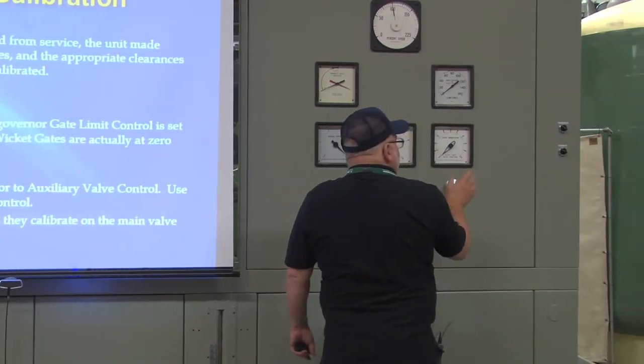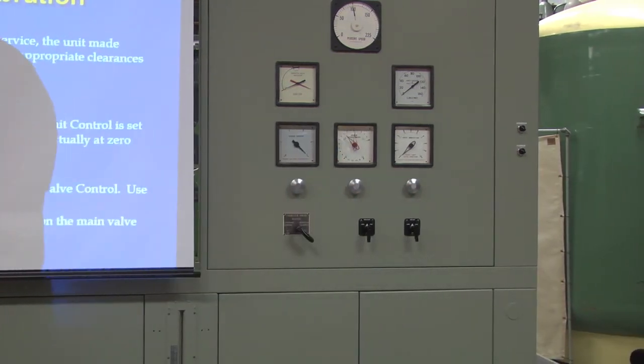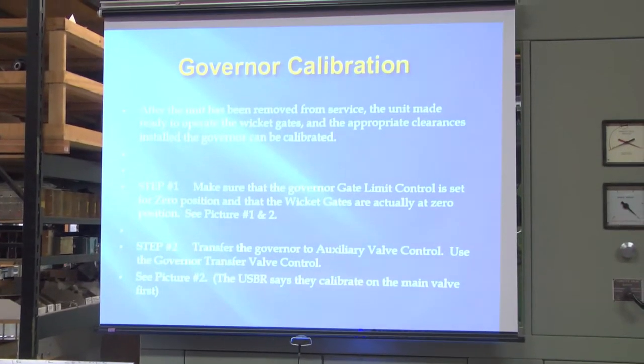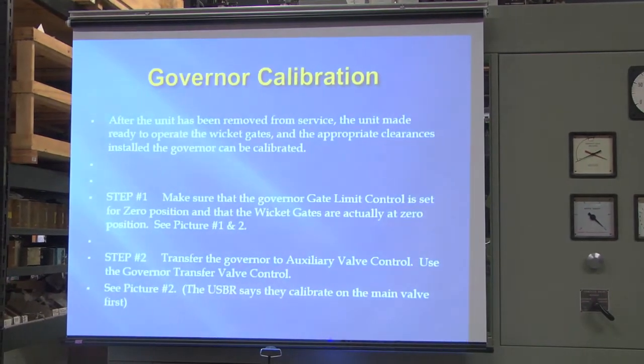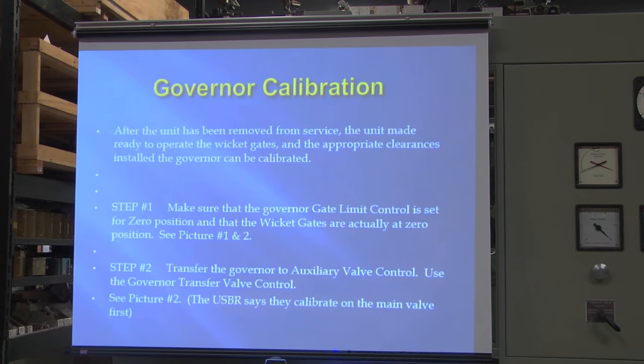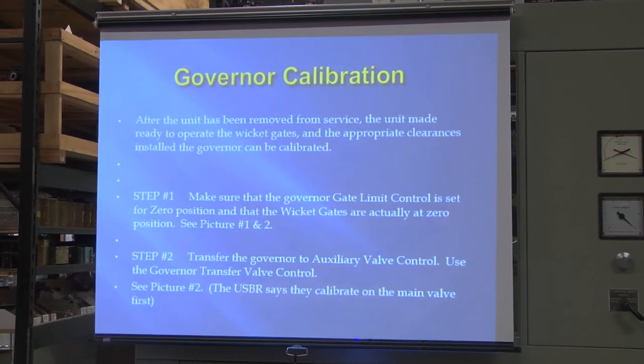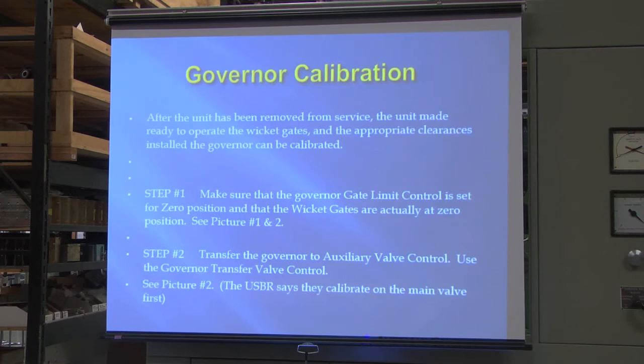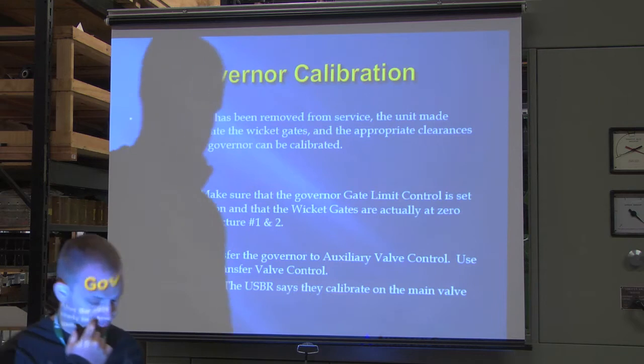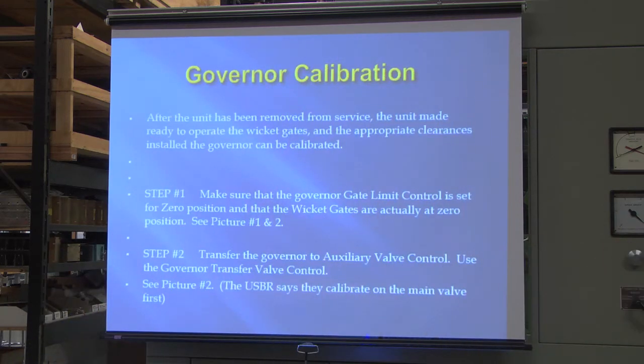And then we'll go through a calibration, all right? Step 2, transfer the governor valve to auxiliary valve. It'll be the first one we calibrate. Now, I'm never too picky on the auxiliary valve, because what's it for? It's for overspeeds and maintenance, to put the wickets in a position, just to stroke, maybe for air, for somebody welding on a runner who wants air to go out the top for ventilation. If he's in the runner, then you have to run the blocks on right where it is so nothing pinches him, okay?